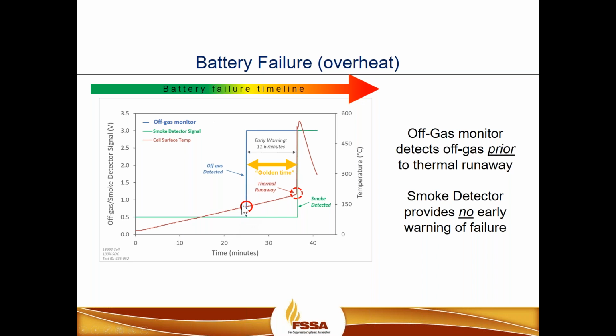And about 25 minutes into the test right here is where the cell begins to off-gas, and the off-gas monitor detects the event. And this is really where we're talking about that golden time factor, the difference between the off-gas being detected and thermal runaway being achieved right here in about 36-37 minutes. So that golden time factor that we talked about earlier, that early warning detection, really for this particular example was a little over 11 and a half minutes.